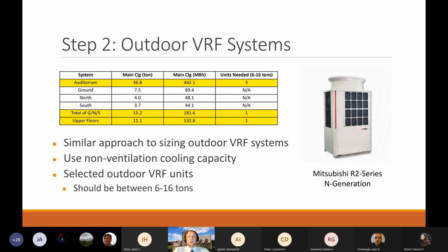And we determined based off of this that we needed to select 3 units for the auditorium and then 2 units for the rest of the building. We wanted to stay with one manufacturing brand as much as possible, and Mitsubishi provided an extensive lineup of VRF equipment, so we decided to stay with them. We selected the R2 series N generation outdoor units for all 5 of our units. We had 3 14-ton units for the auditorium, and then 1 16-ton unit for the ground, north and south systems, and then 1 12-ton unit for the upper floors.